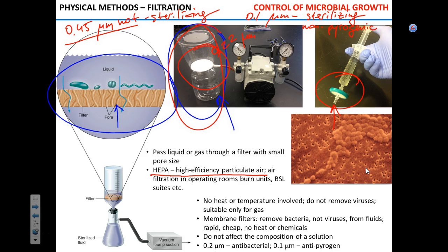Luckily, the BSL-3 unit is built not only in the way that air goes in, the floors in the BSL-3 are lower than the floors of the outside facilities. So in case of water leakage, the water doesn't leak out potentially contaminated water. Turns out in the morning there was ankle high water. It didn't leak. It was ankle high. And we had to dress in BSL-3 suits like the one I showed you yesterday, with the air pump and the hood and everything. And we spent about a day just cleaning the facility from water.